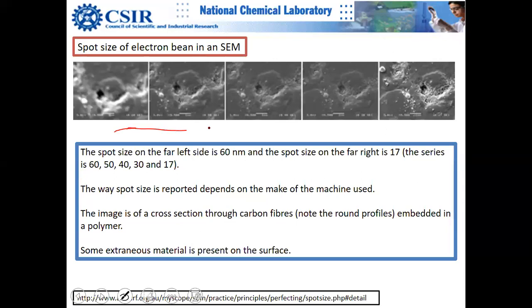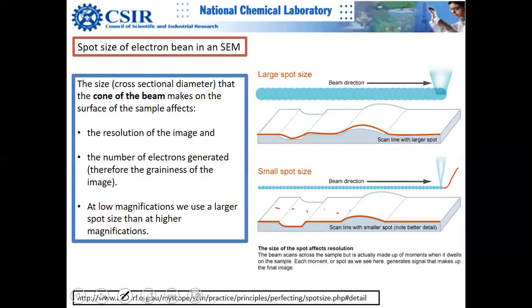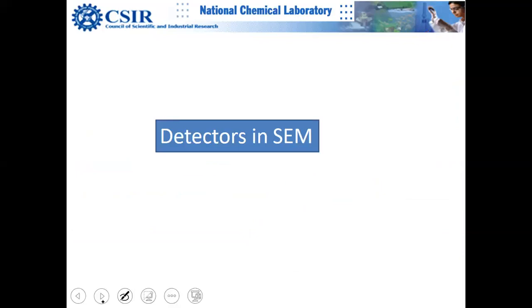Decreasing spot size along this series — from 60 nanometers to 50, 40, 30, and 17 nanometers — the image at 17 nm spot size looks the crispest compared to the others. This proves we need smaller spots for better resolution. Resolution in SEM depends on spot size as well as sample type and topography.